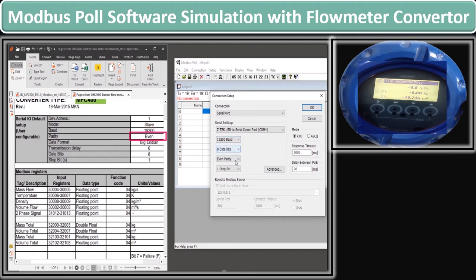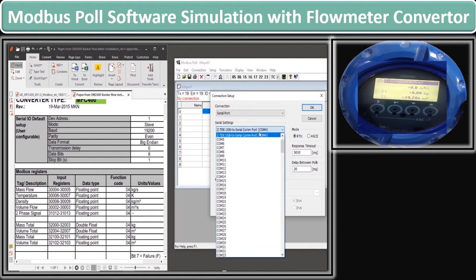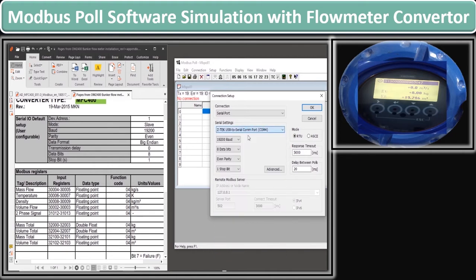Similarly, parity is defined as Even in the parameter list, so we define Even parity in the configuration. Data bit is defined as 8 in the parameter list, so we have given 8 bits in the configuration. The same is done with the stop bit — stop bit is given as 1 on both the configuration and the provided value list. Also, serial communication port is given as COM4 as we have already checked in our Device Manager. Once all parameters are defined similar to the provided parameter list, click OK.